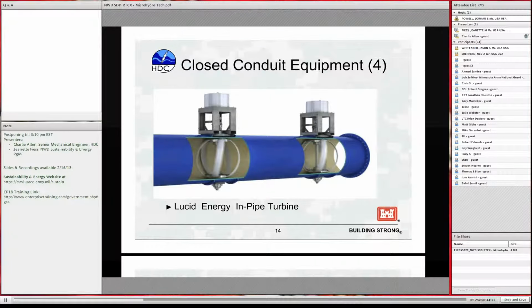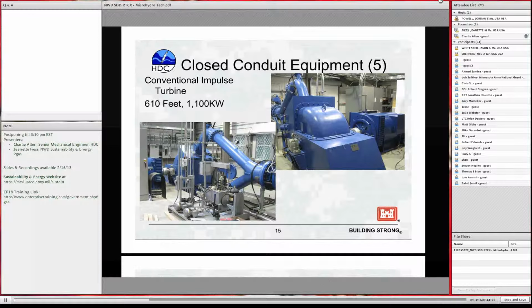This next slide is of Lucid Energy's in-pipe turbine. This is a very new technology with a new application, classically used to replace a pressure reducing valve. You get a section of pipe where you need to drop the energy or pressure, and install some of these in. I think the energy generated by each of these turbines is on the order of 5 to 25 kilowatts, but you can cascade them relatively close to each other. It's an emerging technology just starting to come online, and I don't know how many of these are installed in the United States.